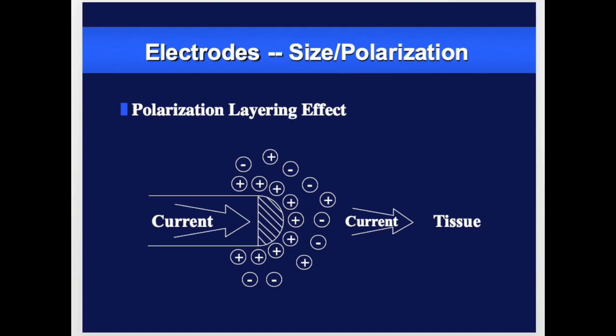The capacitive effect refers to the buildup of a layer of charge on the electrode called polarization. Polarization impedes current flow from the electrode into the tissue. When polarization is excessive, a substantial amount of lead current must be used to overcome it, and less current is available for stimulation of myocardium. As a consequence, the output voltage must be increased and more lead current is required to maintain an adequate tip electrode voltage and a 2:1 safety margin. This high polarization can be overcome by changing the surface structure of the electrode, as discussed in following slides.